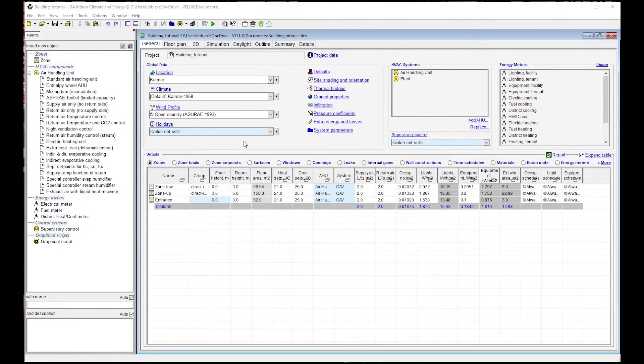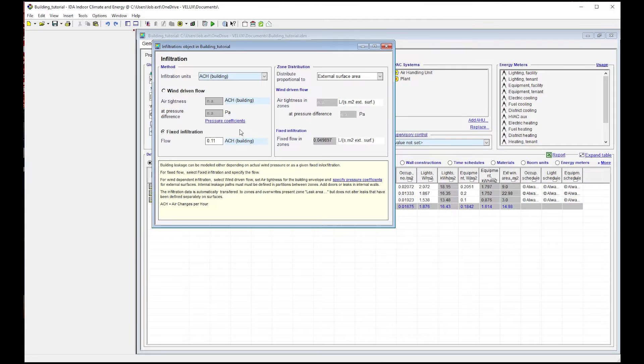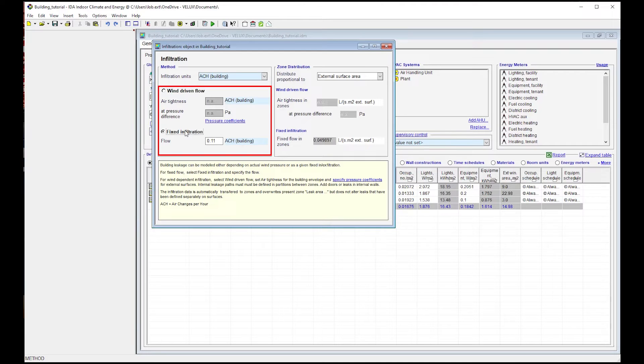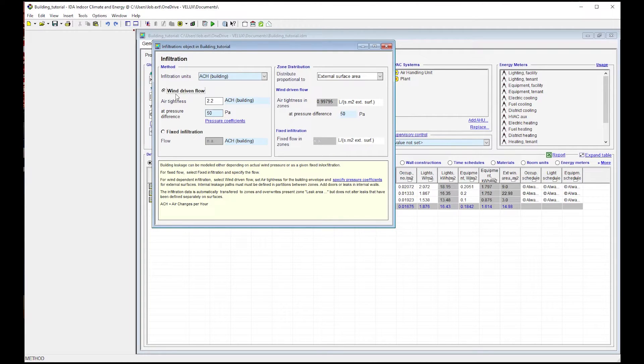The next element that needs our attention is infiltration. Infiltration can be defined in two different ways: wind-driven or fixed infiltration. The fixed infiltration is a simplified mode which assumes a nearly constant air exchange between indoors and outdoors through the construction independently from the wind conditions. In reality, infiltration is driven by wind pressure, and therefore the wind-driven mode is a more realistic option. The programme will calculate the air exchange rate through the construction depending on the wind conditions at each time step.